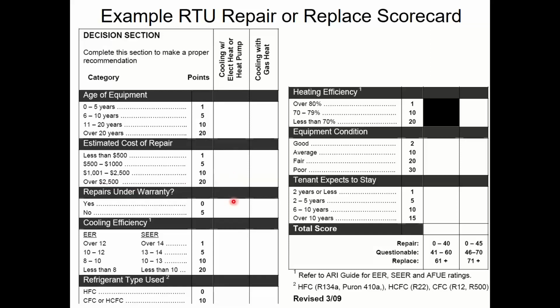Right? Are the repairs under warranty? If they're under warranty, that's great, right? If they're not under warranty, bad points. What's the cooling efficiency of the system? Right? So you put that in there. The less efficient it is, down here in the bottom, the more bad points you get. The more efficient it is, the less bad points you get, right? Because the less efficient it is, that means it's costing me operating energy later on.